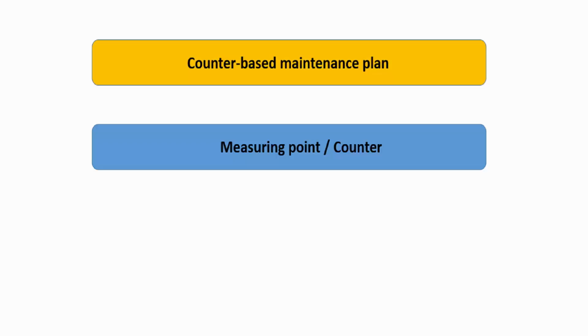For example, in the reservoir of a clarification plant, the volume of sewage that flows out of the drainage channels into this reservoir is measured in cubic meters. Counters are a special form of measuring point because over the course of time, counter readings only either continuously rise or fall. Counter overflow is also possible in the case of most counters. For example, a mileometer can display a maximum value of 99,999 miles. Once this reading has been reached, an overflow occurs, in other words, the counter starts to count upwards from zero again.